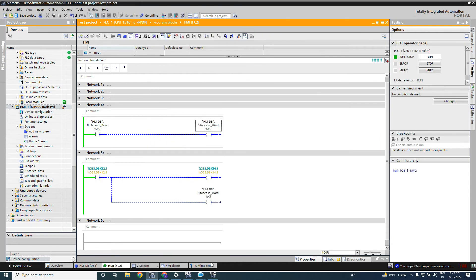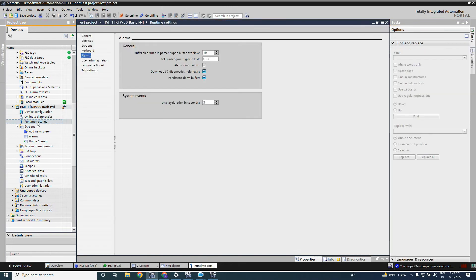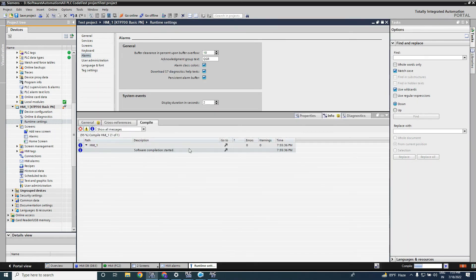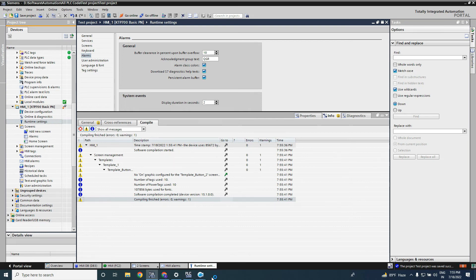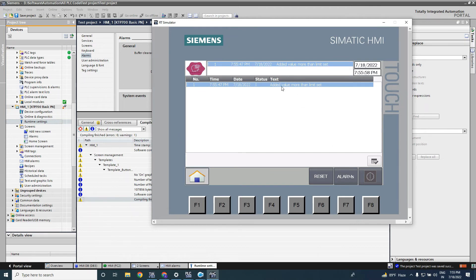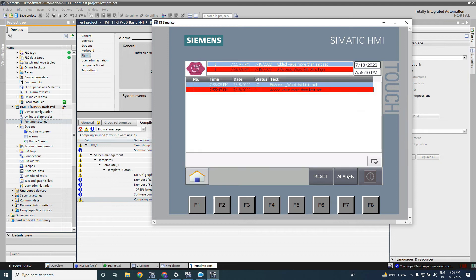If you want to see the alarm color, you have to go to the runtime settings. Under alarm settings, you can see the alarm class color — if you tick it then you can see the alarm color. Now you have to simulate again to see the color. You cannot see it clearly when selected, but if you change the selection color it becomes visible.